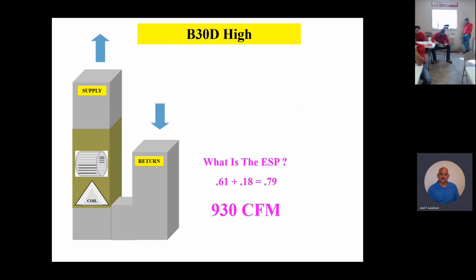And if I was going to remediate this, and here's the homeowner complaint, I love your unit, but it sure seems noisy. It sounds like it's whistling out of the register, where the air comes out. So we've got some pretty high static pressure on that supply. And if I was going to remediate this duct system, I would start looking at the supply side, because that's where the highest static is on this.